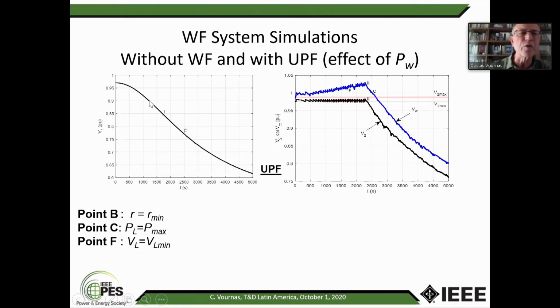Here you see the primary voltage. You see it falls quite a lot. This point C here is where the maximum power to the load is encountered, okay? Because this is very low voltage, we have the case with point F, which we assume is the voltage static limit. So if the voltage falls below a value here, 85%, we assume that you have a low voltage limit. So point F marks the low voltage limit, point C marks the maximum power limit.